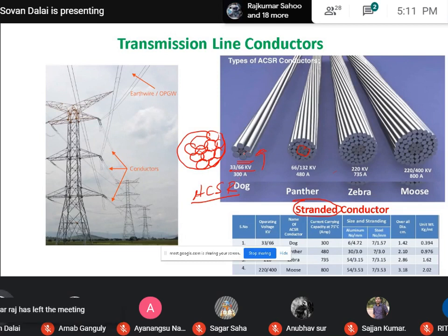So 6 conductors surround one single steel conductor. The total number of subconductors present in the strand is 7, and generally this conductor is capable of delivering a current of 300 ampere. This type of conductor is named like animal, dog conductor, panther conductor, zebra, and moose conductor. According to the voltage levels, you see the current rating capacity gradually increases. So these are basically called the stranded conductors.